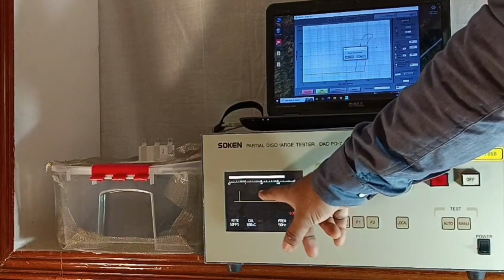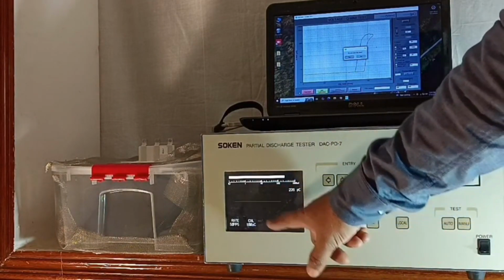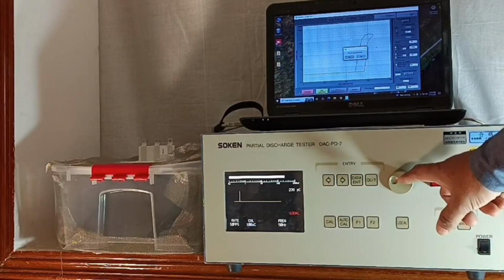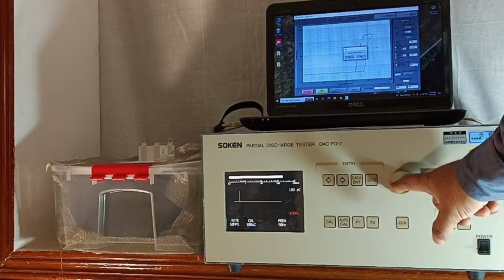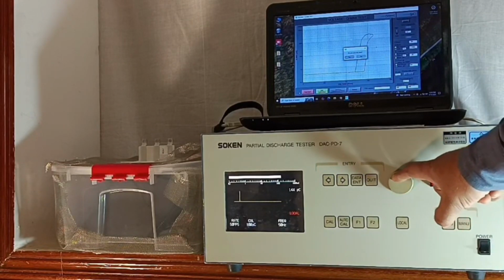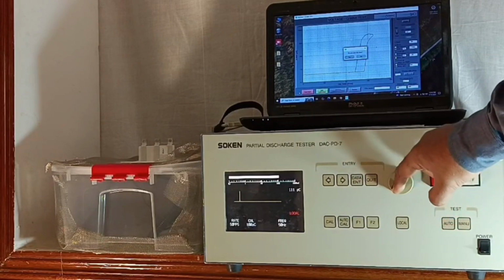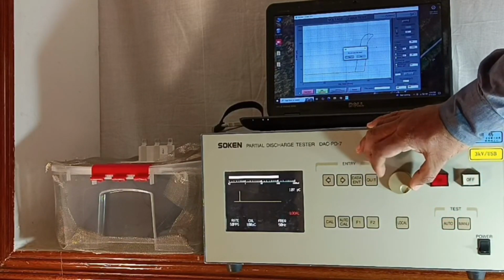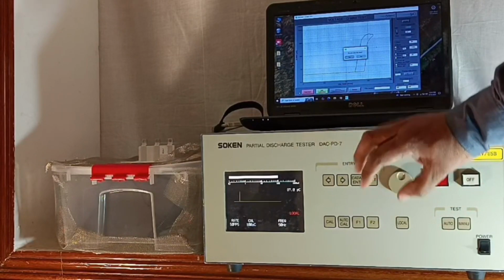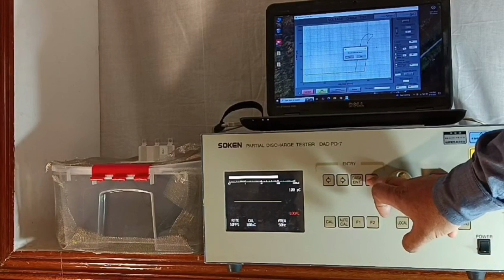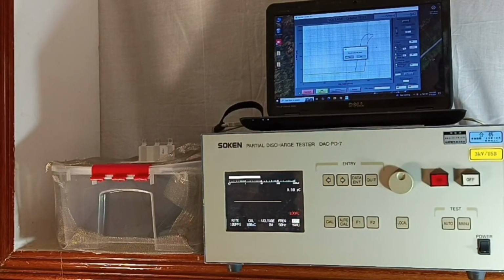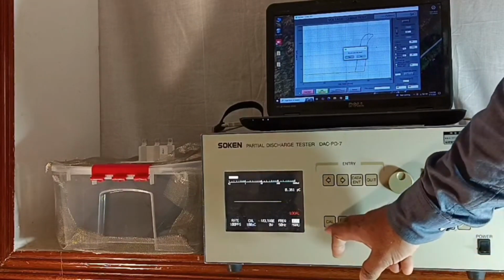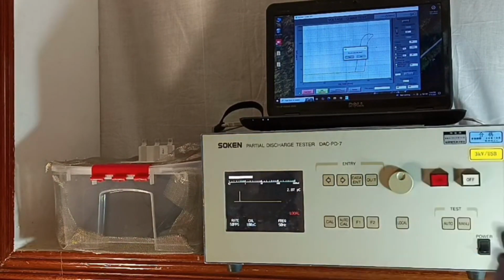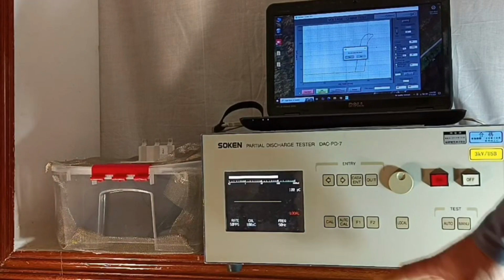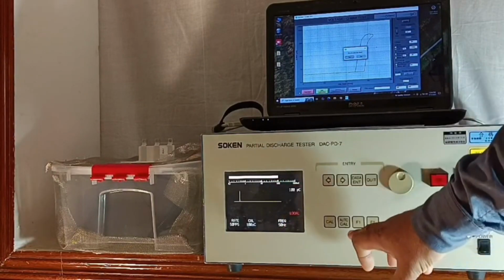Now this is a manual, we have to calibrate. I press the calibration pulse. Calibration pulse is available here, and you have to adjust the gain in such a way that the pulse of 100 PC is displayed on the meter. Now it is manually calibrated. You can quit. To verify, we can again give the calibration pulse. It is 100 pC. So the gain is set, and whatever the 100 pC applied, now it is displayed.